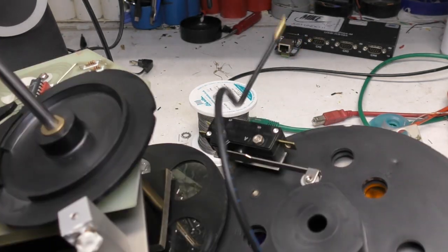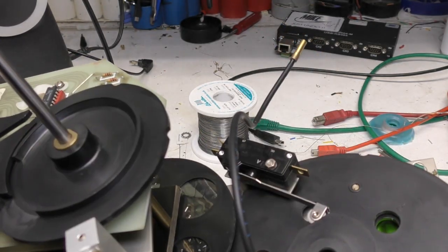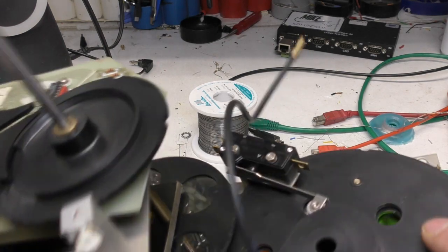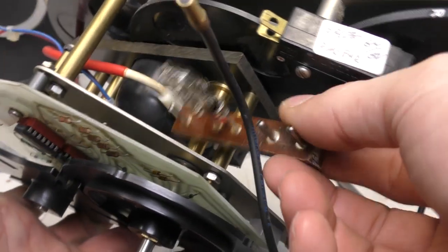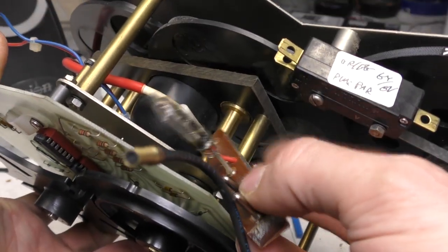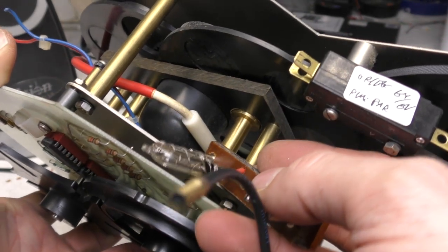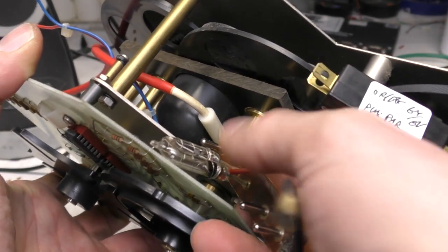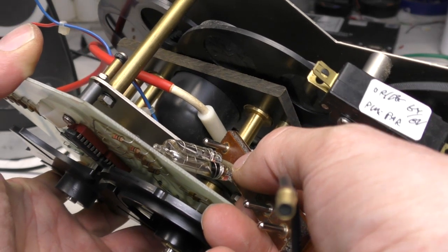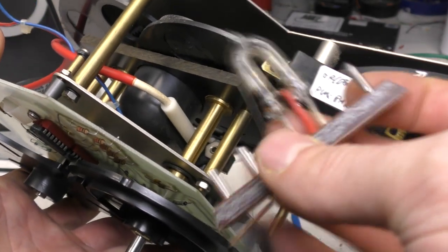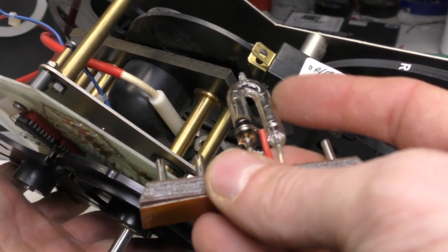And so there's this micro switch that operates when the blue filter's present, so I haven't quite figured out what that actually operates. And one bit of really poor design on here: the flash tube. The way these flash tubes work is you've got a capacitor which is charged up to around 300 to 400 volts, and then there's a high voltage trigger impulse that actually triggers it, and this is coupled to this, which has actually got wire wrapped around it.